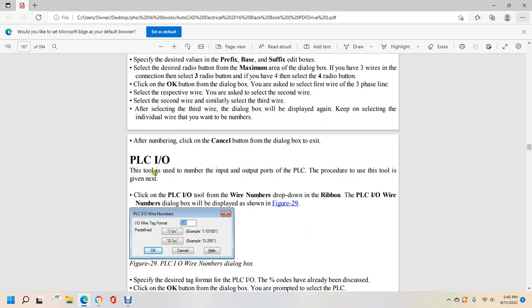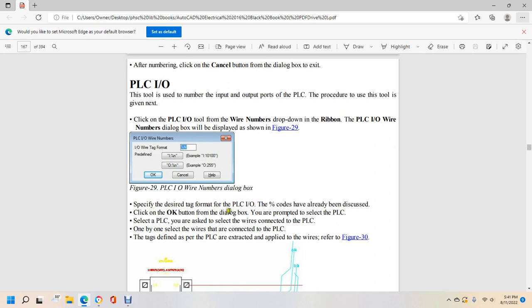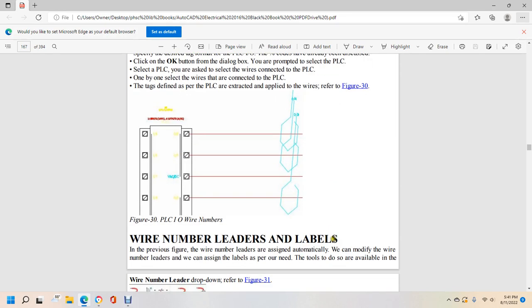PLC I/O wire numbering. This tool numbers the input and output ports of the PLC. Click the PLC I/O tool from the wire number drop-down ribbon. The PLC I/O wire number dialog box will display as shown in figure 29. The I/O wire tag format pre-define and PLC wire number settings are available. Click OK, then select the PLC and the wires connected to it one by one. Tags will be defined, extracted, and applied to the wires as shown in figure 30.